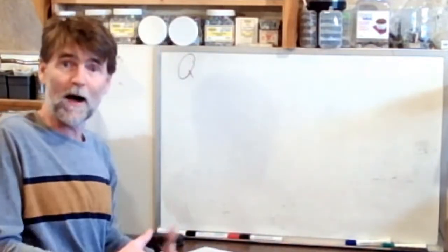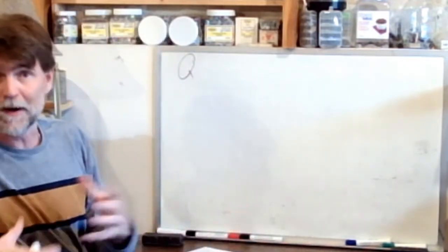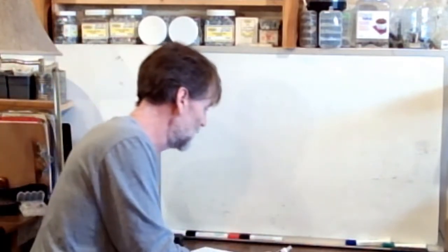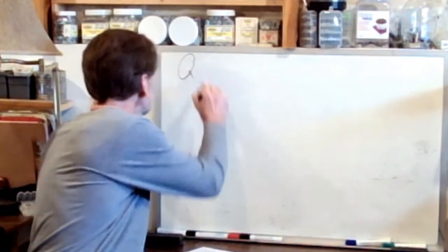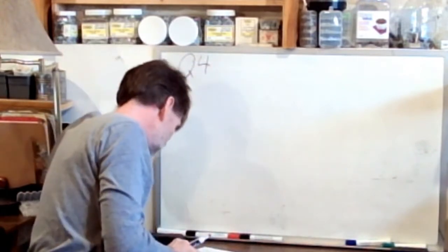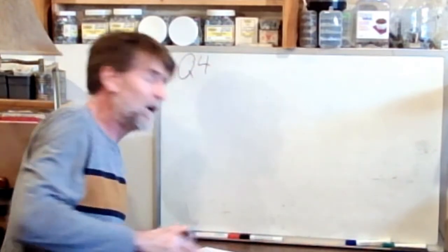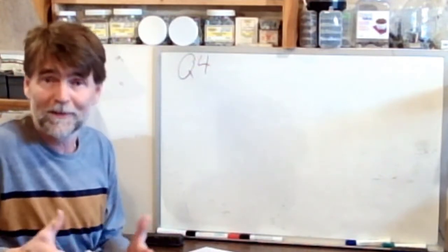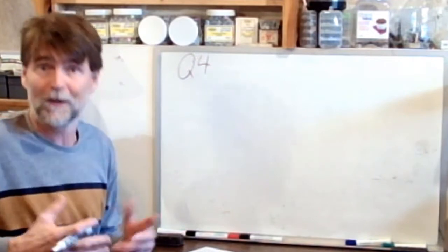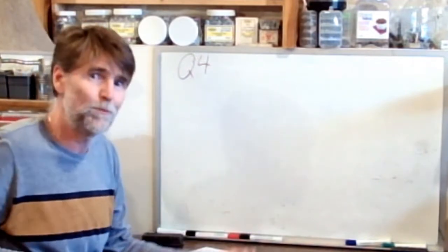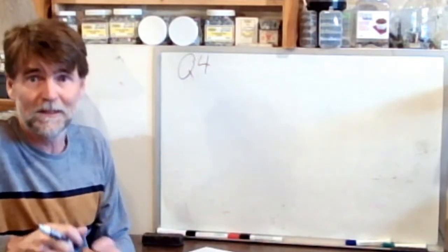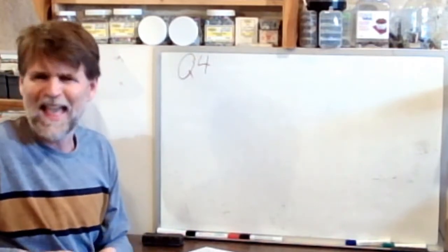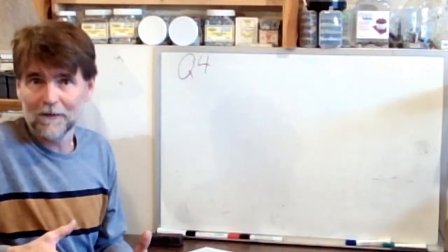Because question 4 and 5, they introduce some other components. So it's a nice opportunity to talk about some other things as we go along as well. So question 4, it's a tungsten filament. That's the first piece of information. All that means, the only thing that changes is our value for K. We're going to have to know what that is. It's 10.4 for copper. It's 17 for aluminum. I do expect you guys to remember those numbers. Anything else, you'll be given that information.